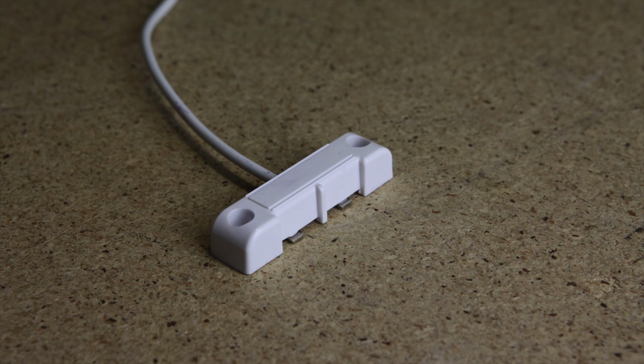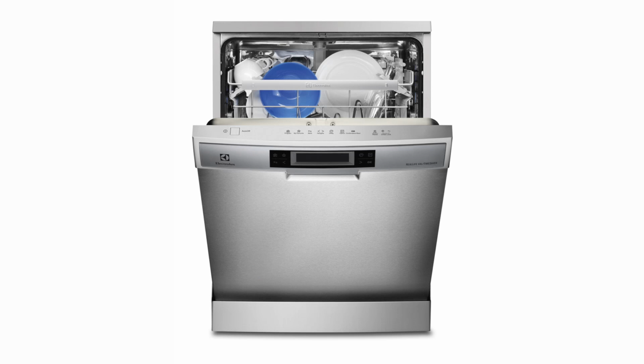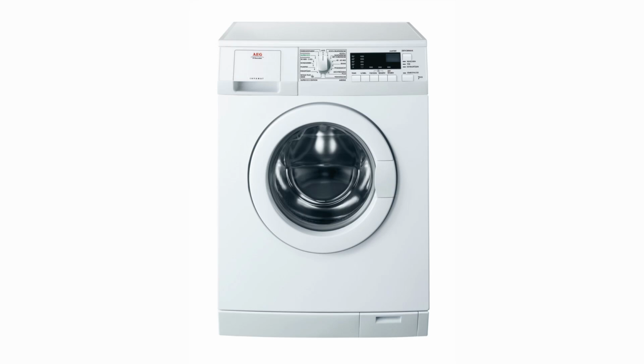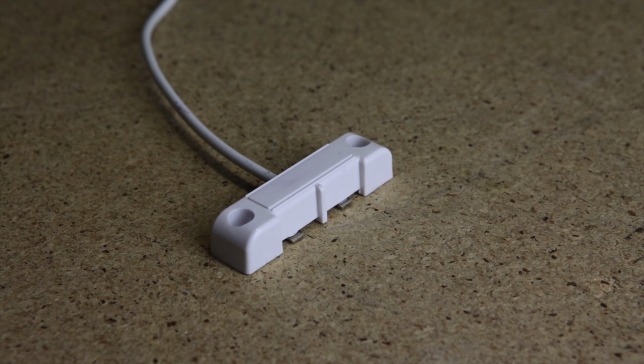Wireless wetness sensor. You can add optional wireless wetness sensors to the system. The sensors can be placed in locations where burst pipes or leaks are more likely, like behind dishwashers and washing machines. These sensors can be linked wirelessly to the AquaTrip, and if any of them detect a leak, they will signal the control unit, which will then shut off the water within 1 minute.